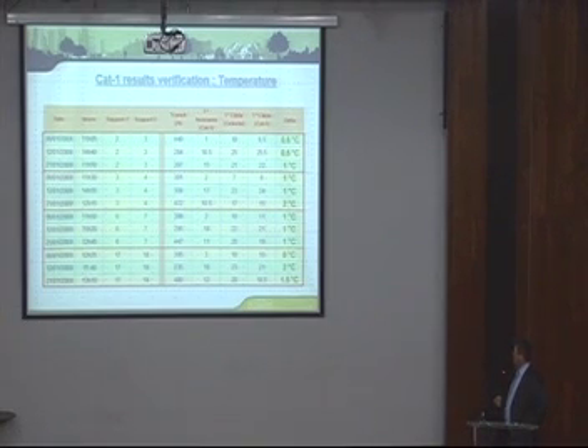I don't know any way how you can get to this, well, maybe if you put a fiber optic into the conductor which measures continuously along the section. But that's our experience: tension with the accurate calibration is maybe the most accurate way to determine the average conductor temperature, which sounds strange, but as you might remember, all these weather impacts make it difficult to get the local conditions. For operating purposes, only the average conductor temperature is necessary, and this is an excellent way to get to that point.